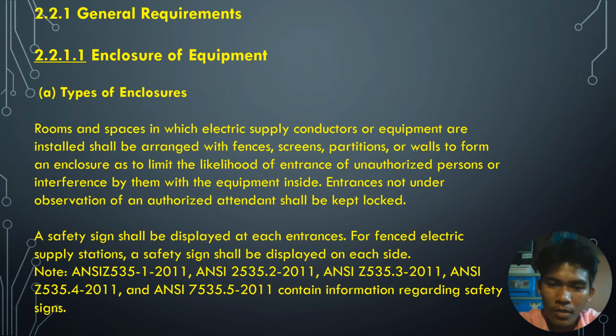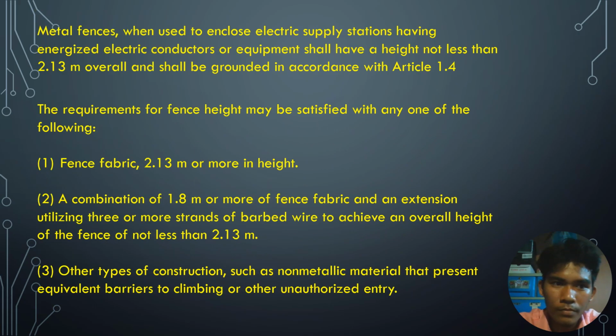Entrances not under observation of an authorized attendant shall be kept locked. A safety sign shall be displayed at each entrance for fence electric supply station. A safety sign shall be displayed on each side. Metal fence, when used to enclose electric supply station having energized electric conductors or equipment, shall have a height not less than 2.13 overall and shall be grounded in accordance with Article 1.4.